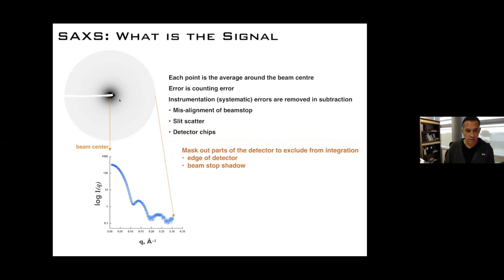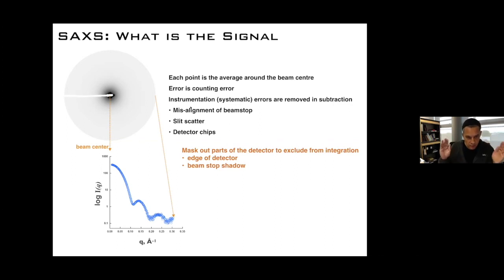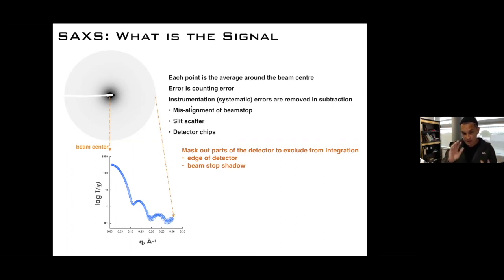The errors are typically errors in counting. As you go around in the circle you have counts on the pixels, so you're doing Poisson counting statistics. If there are any issues with the instrument itself — if the beam stop is misaligned slightly, or you scatter from the slits, or some issue with the detector — typically when you do the subtraction between the buffer and the sample, a lot of these things just subtract out.